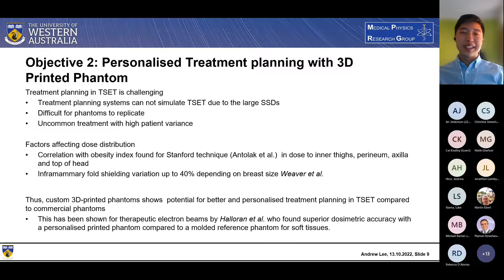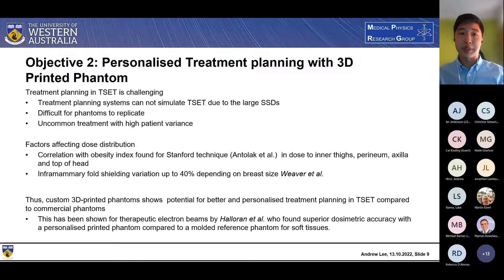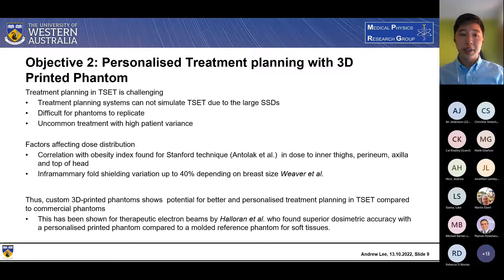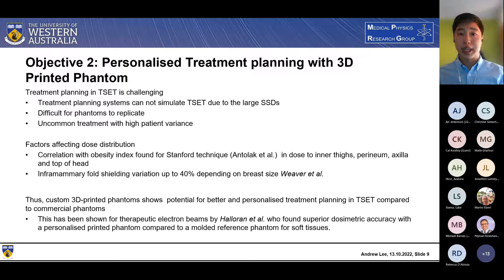Electrons entering at oblique angles show much higher dose variations compared to photon beams. This is emphasized in total skin therapy when dealing with a lot of side angles, and also with obese patients, who have larger radii and thus larger lateral regions with more significant variations. There is also the inframammary fold — the skin under the breast — where for those with pendulous breasts the dose can differ by up to 40%, which is quite significant. 3D printed custom phantoms show the potential for better and more personalized treatment planning compared to commercial phantoms, and have been validated for electron beams showing higher accuracy compared to reference molded phantoms.